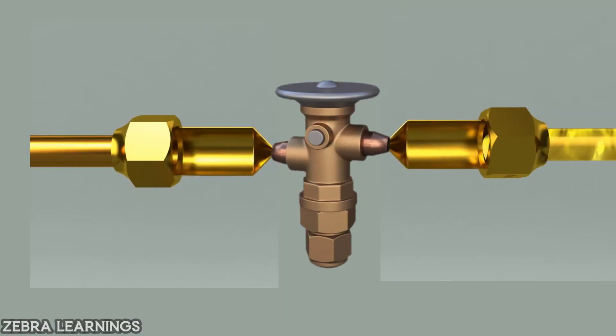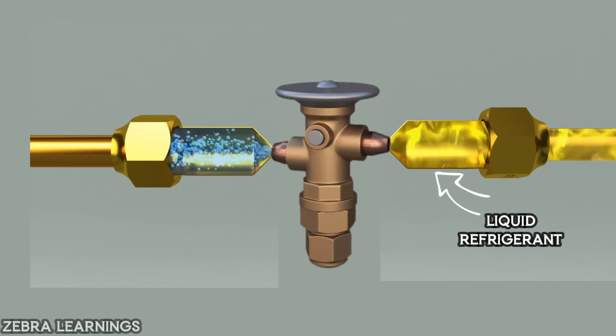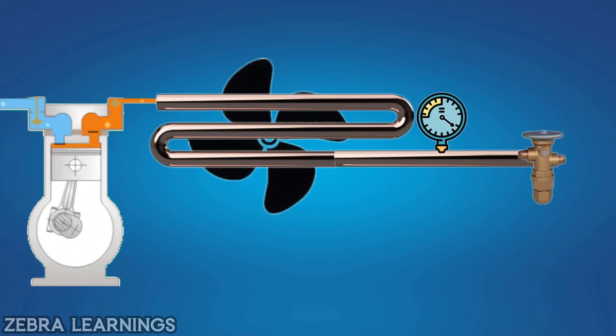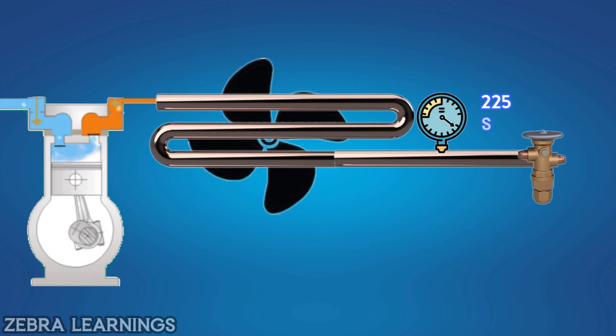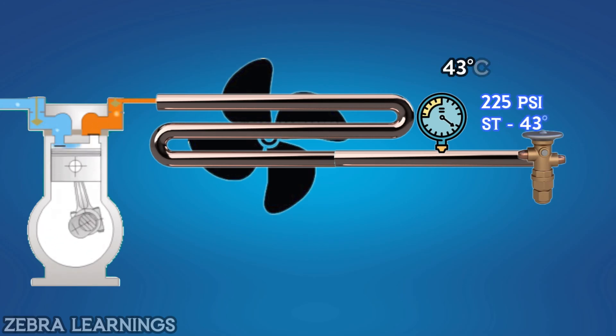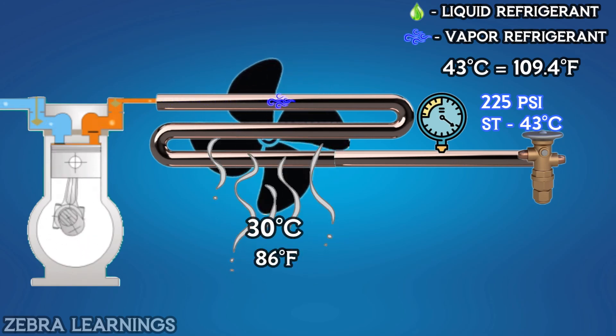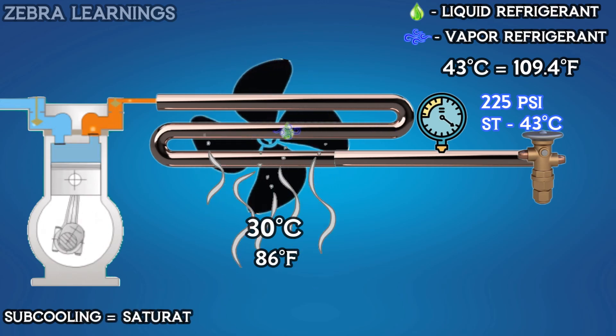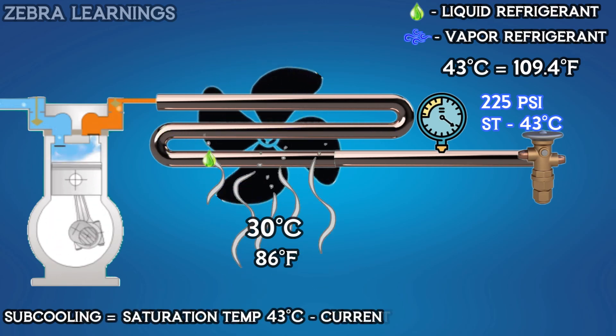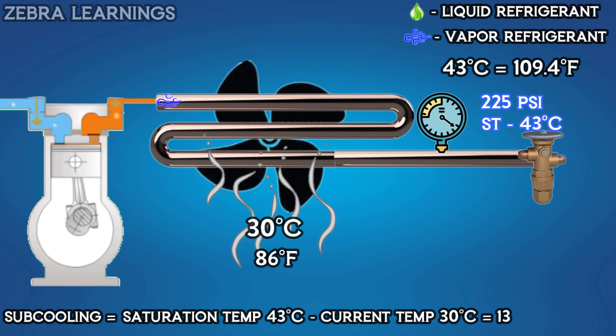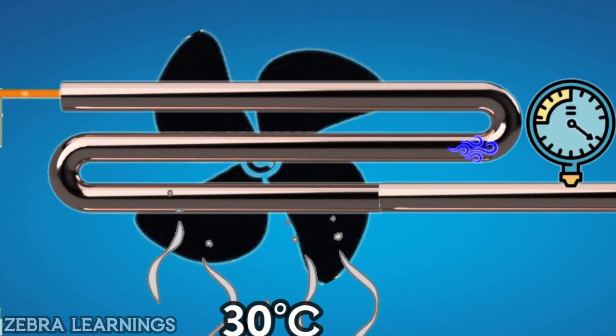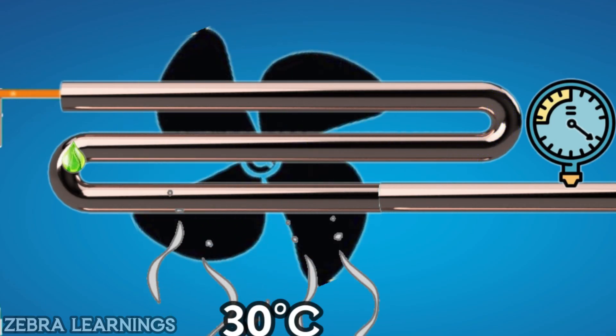When the refrigerant goes inside the expansion valve, it should only go in liquid form — only then can we get proper cooling. If the R22 refrigerant inside the outdoor unit is at a pressure of 225 PSI, its saturation temperature will be 43 degrees Celsius. If we cool the outdoor unit to 30 degrees Celsius, the subcooling value is: saturation temperature 43 degrees Celsius minus current temperature 30 degrees Celsius equals 13 degrees Celsius. So if we cool the refrigerant below 43 degrees Celsius in the outdoor unit, all the refrigerant turns into liquid state.